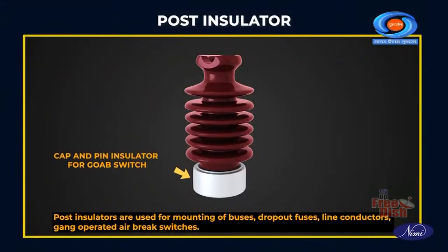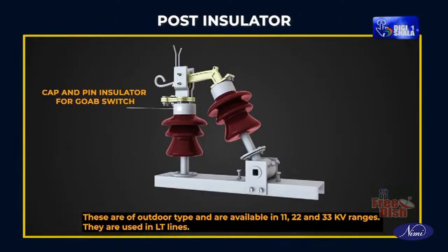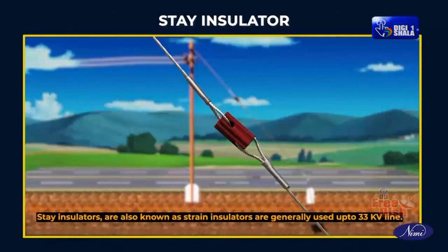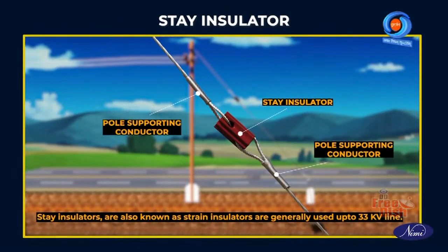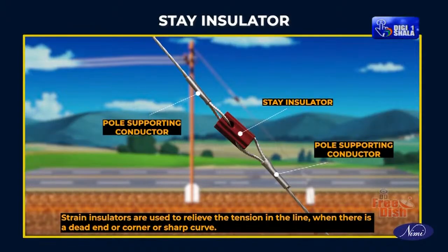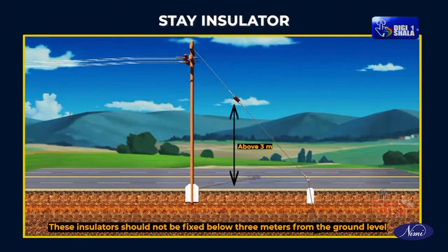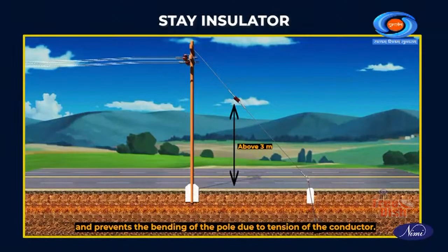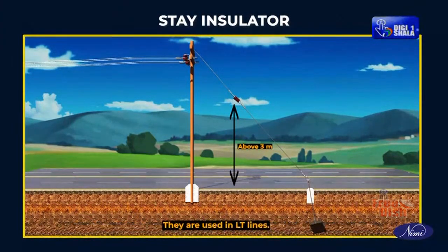Post insulator. Post insulators are used for mounting of buses, dropout fuses, line conductors, gang-operated air break switches. These are of outdoor type and are available in 11, 22 and 33 kV ranges. They are used in LT lines. Stay insulator. Stay insulators are also known as strain insulators and are generally used up to 33 kV line. Strain insulators are used to relieve the tension in the line when there is a dead end or corner or sharp curve. These insulators should not be fixed below 3 meters from the ground level and prevent the bending of the pole due to tension of the conductor. They are used in LT lines.